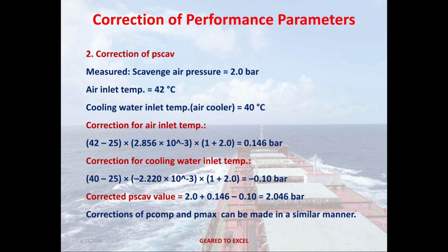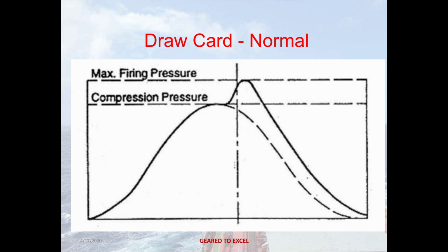Let's talk about the draw card. This is a normal draw card where the maximum firing pressure is at optimum and the compression pressure is also at the optimum. So these are the standard reference lines for this draw card for maximum firing pressure and compression pressure, and this is the curve for the Pcomp and the Pmax. Let's see if there is some fault in the draw card, what it interprets.